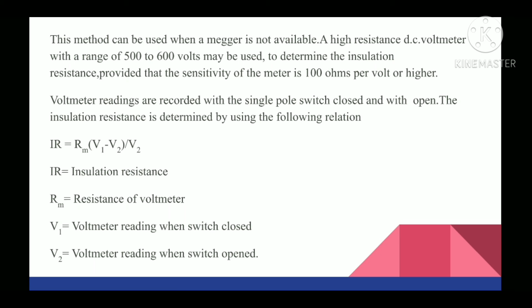The insulation resistance is determined by using the following relation: IR = RM (V1 - V2) / V2. IR is the insulation resistance, RM is the resistance of the voltmeter, V1 is the voltmeter reading when the switch is closed, and V2 is the voltmeter reading when the switch is open.